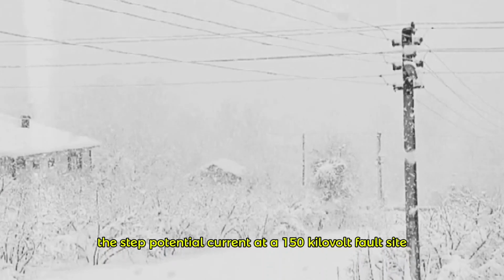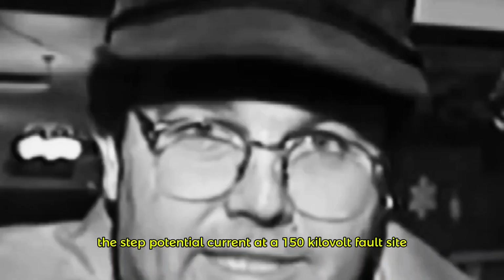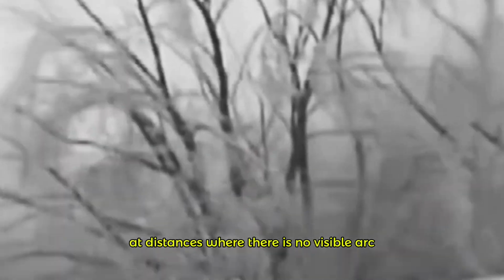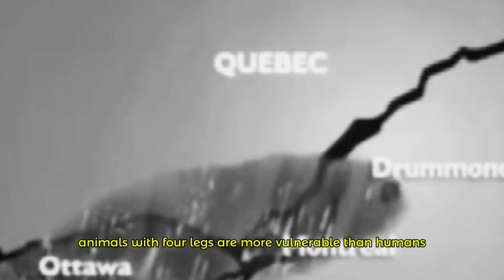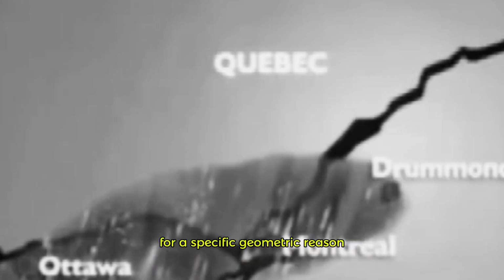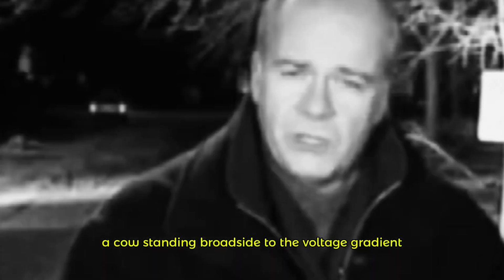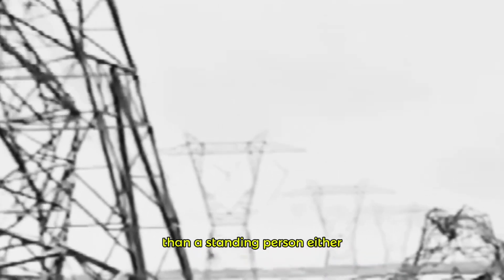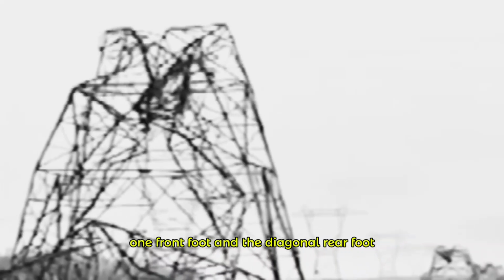The step potential current at a 150 kilovolt fault site exceeds that threshold by a factor of 10 to 20 at distances where there is no visible arc, no audible warning, and no reason to believe the ground itself is the hazard. Animals with 4 legs are more vulnerable than humans for a specific geometric reason. A cow standing broadside to the voltage gradient bridges a far longer step distance than a standing person. Either one front foot and the diagonal rear foot can be on opposite sides of a voltage contour, placing the fault current path directly through the animal's chest across the heart.